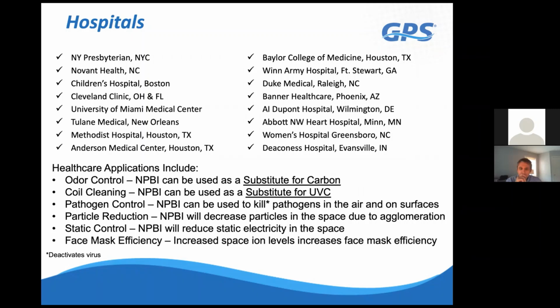Just a couple months ago, they actually put it into their ORs and they did a pre and post testing, and they saw a 70% reduction in total particle counts, even in an operating room where you have 20 plus air changes per hour and HEPA filters. And so this technology really can go after those ultrafine particles, make them get larger to where the airflow can push them around more effectively and get them captured at the filters. So they saw a big particle reduction in the operating room, which is deemed a sterile environment. They also saw a large reduction in airborne viable bacteria, which was also critical in these applications.